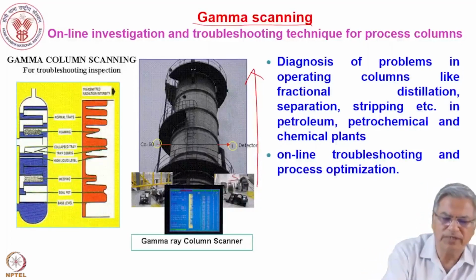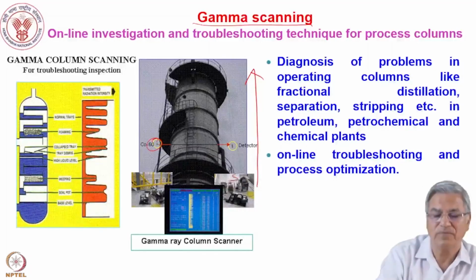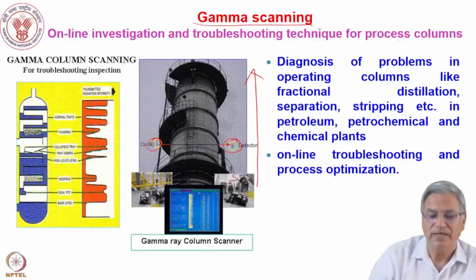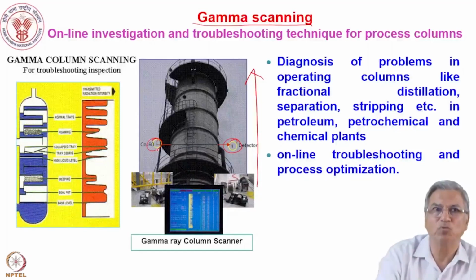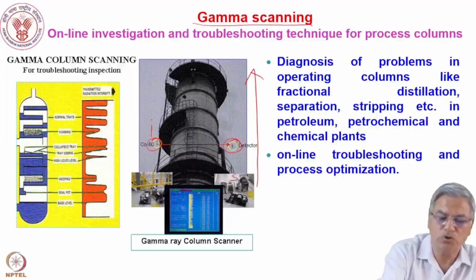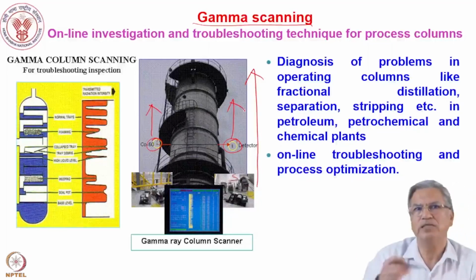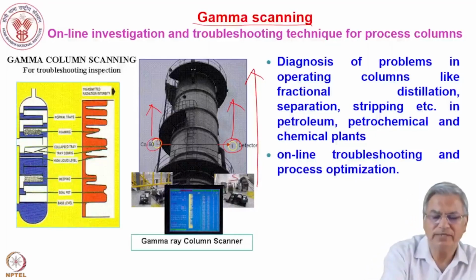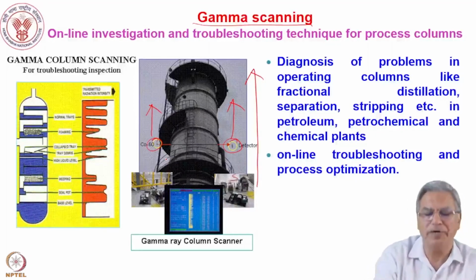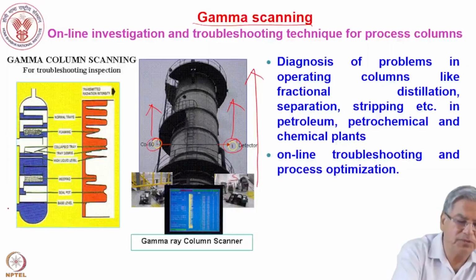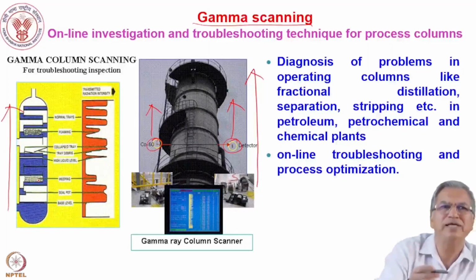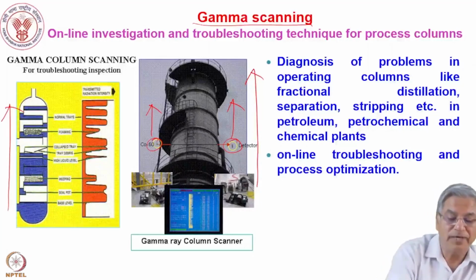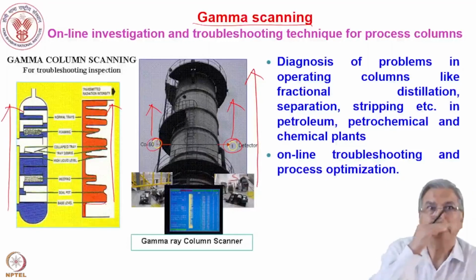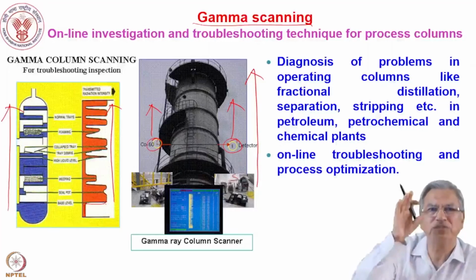You put a cobalt-60 source on one side and a sodium iodide thallium detector on the other, and move them synchronously, joined together so that as the source moves, the detector moves the same amount. What you get is the attenuation of the gamma ray from cobalt-60 as it passes through the internal parts of the column. This column has different plates and fittings inside, and when the gamma ray passes through a thick object, the intensity will be low, revealing the profile of the different internal objects.